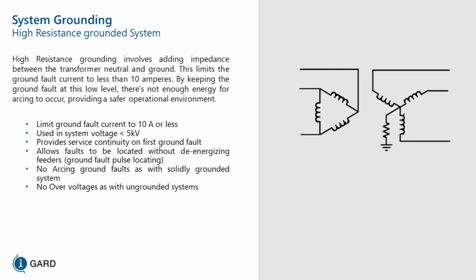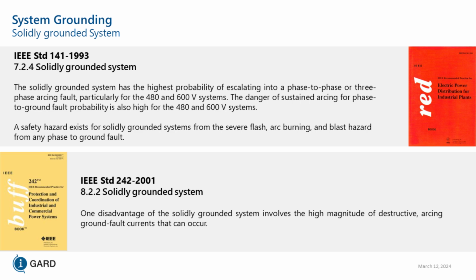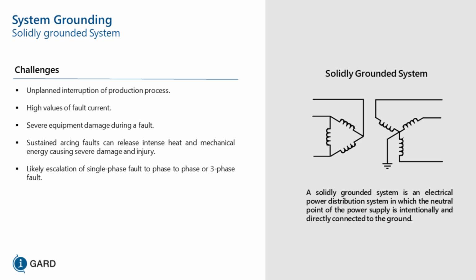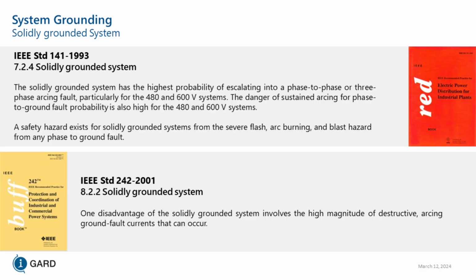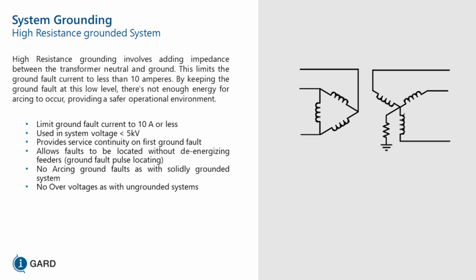You still elevate the neutral, even though the neutral is not distributed. You can't distribute the neutral in a high resistance grounded system, but the neutral gets elevated to 277 volts. Well, 277 volts divided by 55 ohms gives you 5 amps. So you limit the fault current. The same fault that we had in the scenario where we have thousands of amps flowing, we put a 55 ohm resistor in here, and now we have 5 amps flowing. Same size transformer. Doesn't matter if it's 1 kVA, 1 MVA, or 5 MVA. A 55 ohm resistor there will limit your fault current to 5 amps.